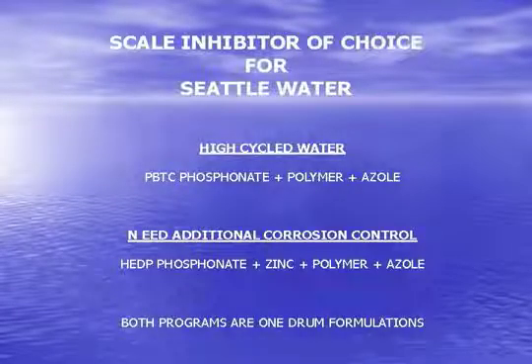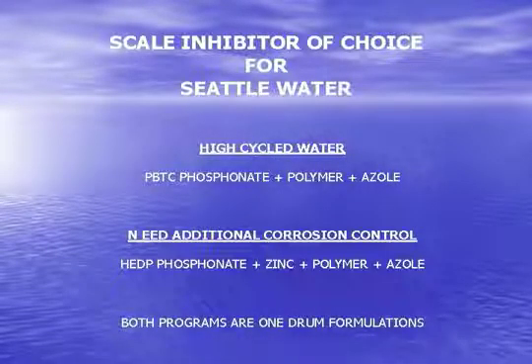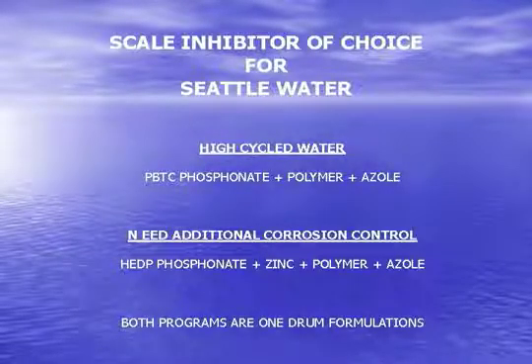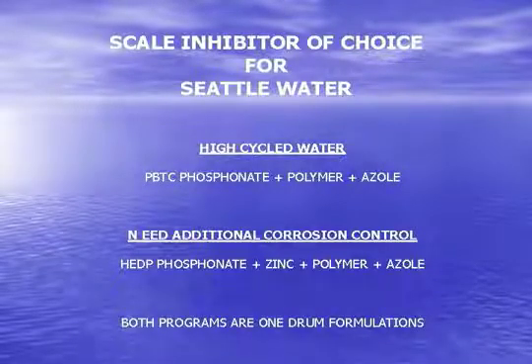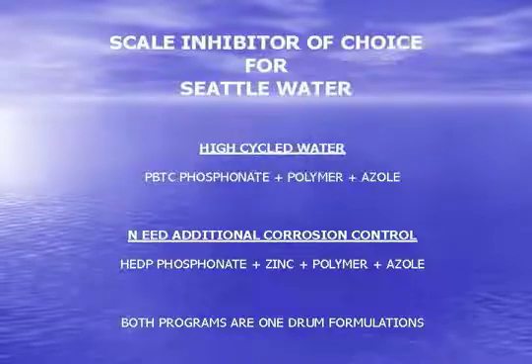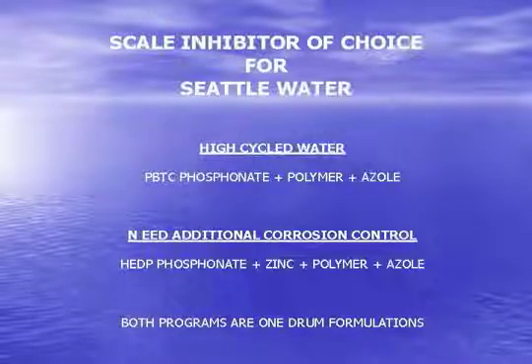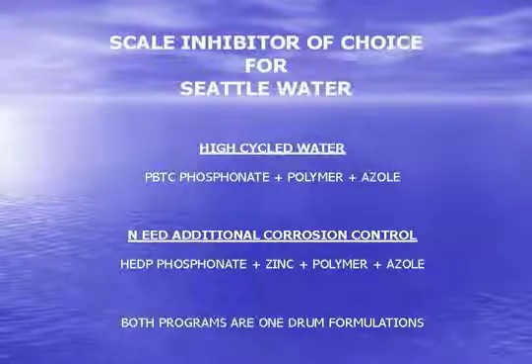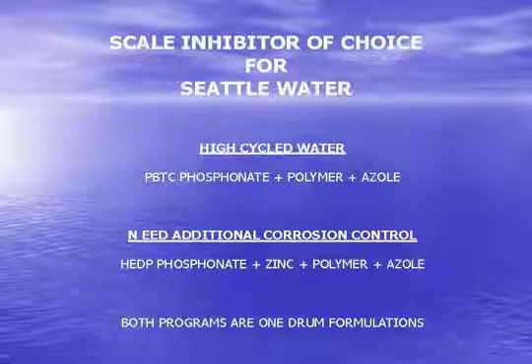Scale inhibitors of choice in Seattle — let's figure out what you should be using. There are basically only two choices that are technically sound for Seattle water. If you're going to push your high cycles — which are 15 cycles of concentration — I recommend the use of PBTC phosphonate. This is a phosphonate designed to handle high-scaling water because we're actually driving the water to a scale-forming state. A PBTC phosphonate blend — most water treatment companies have a polymer they use for suspended solids and azole. Azole is your copper corrosion inhibitor, and we'll talk about that.